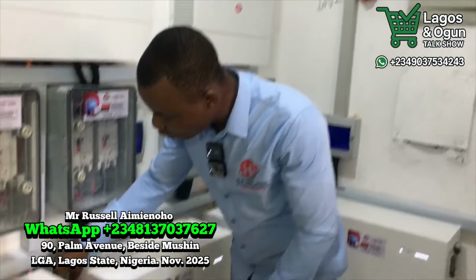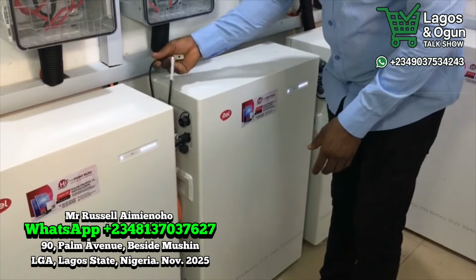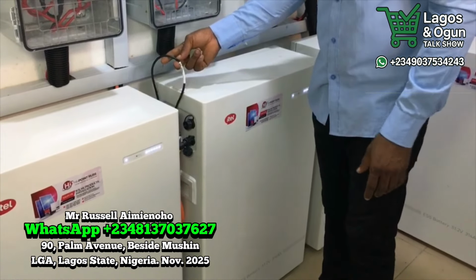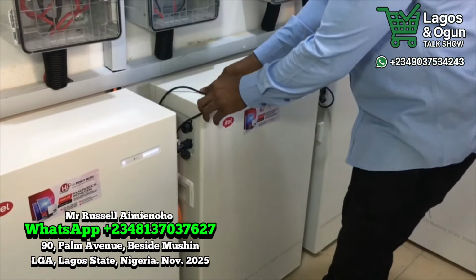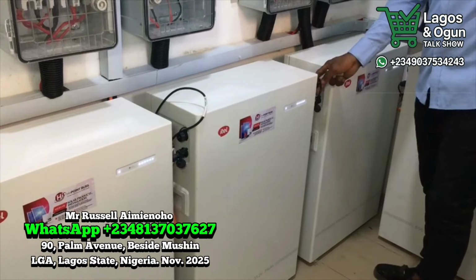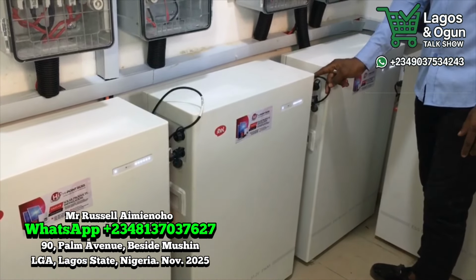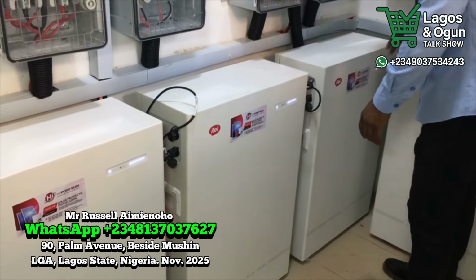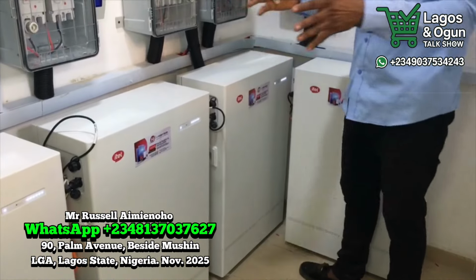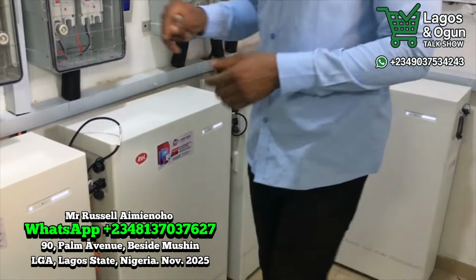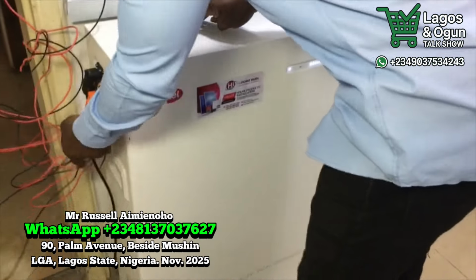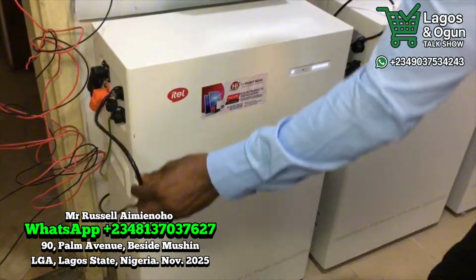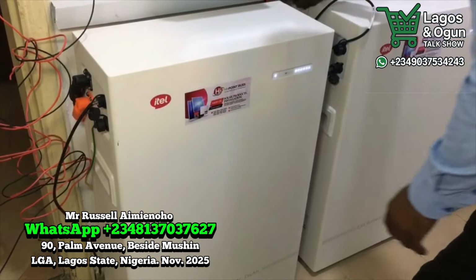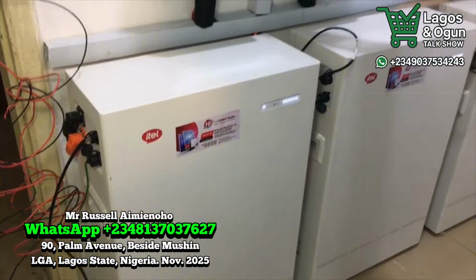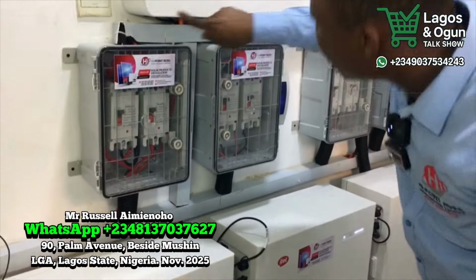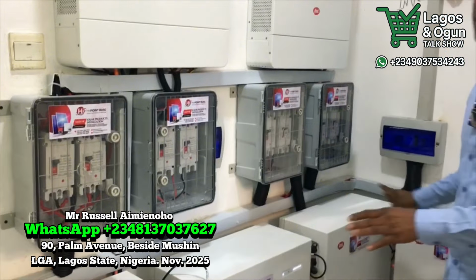Okay, then for here too we can also use the communication cable. You see here, this communication cable, we use this one to link this to this battery, because without this communication cable, the BMS or the battery won't sync. We also communicate here and here together, all of them communicate together. Then this one might be the master battery, others are slave, that's why you see this BMS cable. Now you follow here, enter this port, the BMS port, go connect. All these other ones will not connect the BMS.